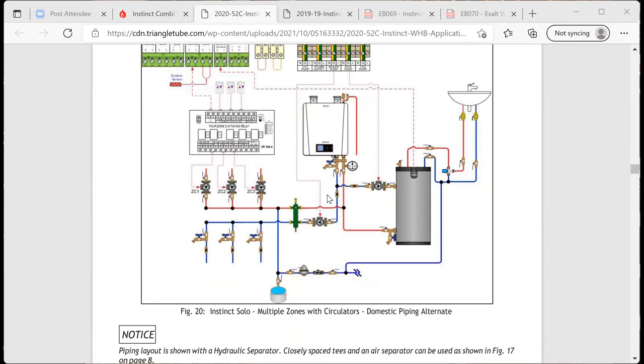So as long as your pump has an internal check right here and here, these are not needed, okay? So the way this works is your heating comes on, the pump pushes water up through this way, the check valve in here prevents the water flow back to your indirect, pumps up to the boiler, out to the supply in the system. That does that little loop right there. Your domestic calls, this pump immediately shuts off. This pump kicks in. Why we need both the same size pumps for flow. This pump pumps in, check valve prevents it from going this way, moves it up to the boiler, out to the supply and through here. This is the way we recommend piping the indirect on the primary side.